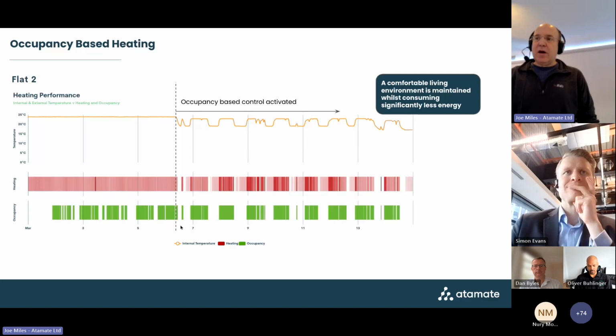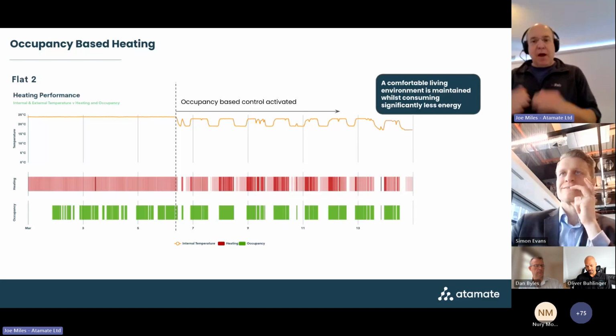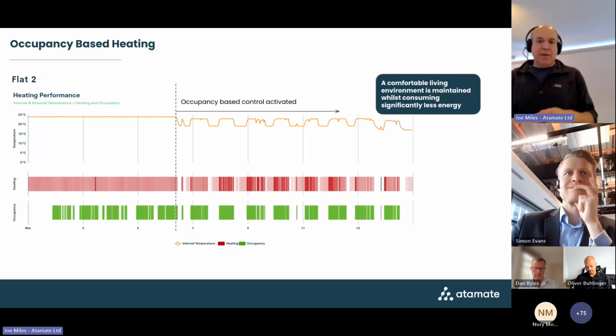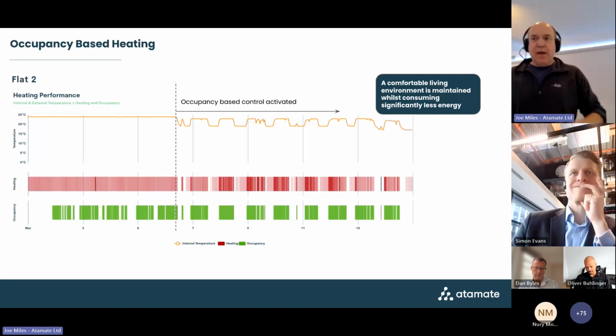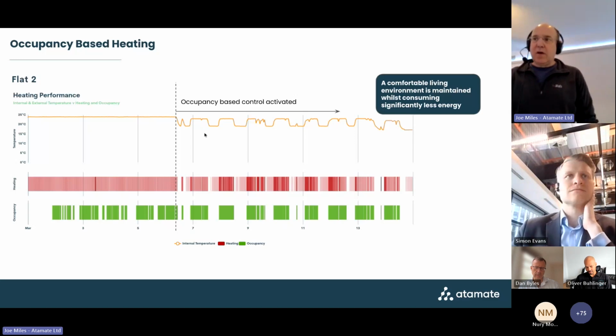What we've done here is turned on the occupancy-based heating, and as you can see now, the temperature profile varies depending on occupancy. Bear in mind, depending on the fabric performance of the building, the setback temperature might not just turn off the heating - we might retain it at a certain level, particularly if it's very cold outside. That's why you're not seeing the heating go totally off, but dropping to a lower level in this building. Again, you can see there's continual occupancy - so this is an example of heating.